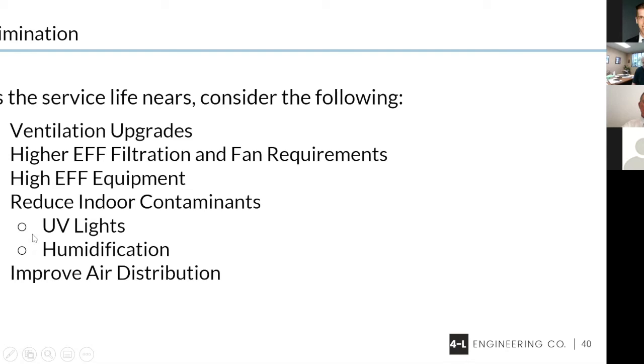It has the ability, and the reason it was created was really for equipment manufacturers to not have to pay so many warranty claims for compressors going out. And the claim was really generated because people didn't change their filter. So they designed a motor that really allowed people to keep dirty filters in for a longer time. The ECM motor will give you the ability to add this extra filtration that I'm talking about.